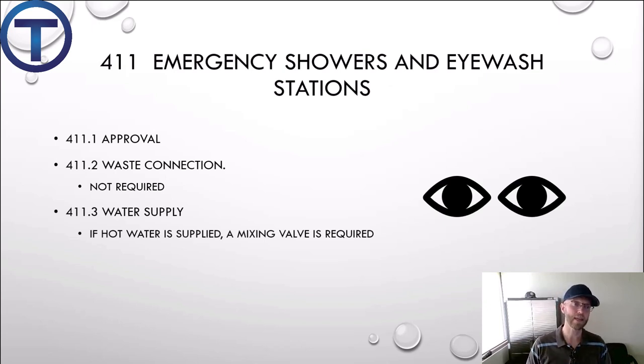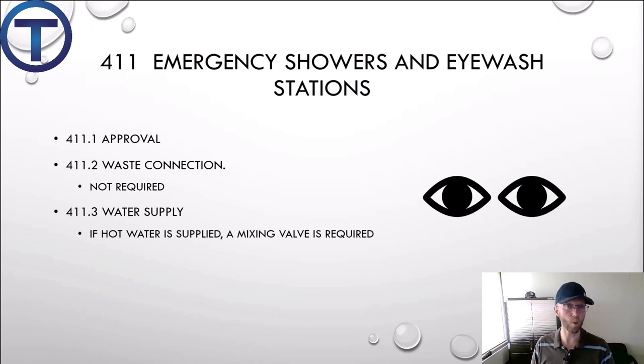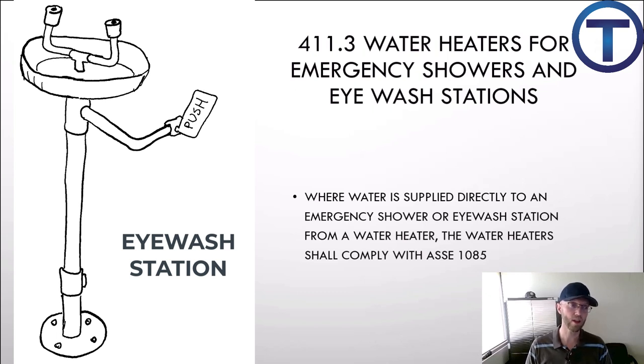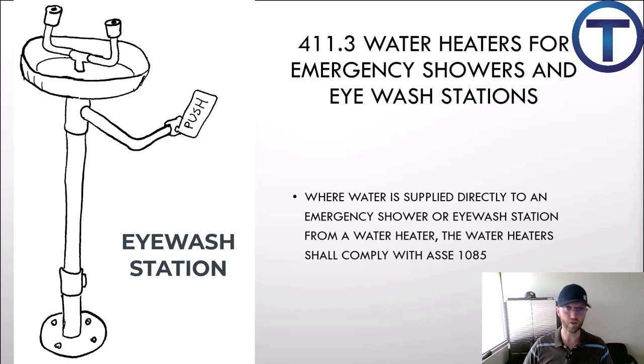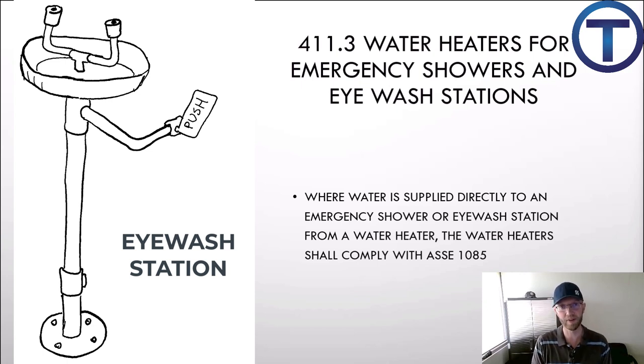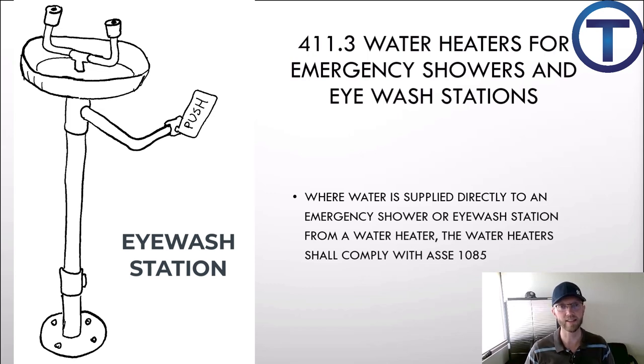In 411, we examine emergency showers and eyewash stations. 411.1 requires them to meet certain approvals. 411.2 states there is no drain connection required for an eyewash station. 411.3 says if warm water is supplied, it has to be tempered down. If you get chemicals in your eye and the eyewash station hits you with 120-degree water, it would scald your eyes on top of the injury — so tempered water is required to avoid increasing pain and injury.